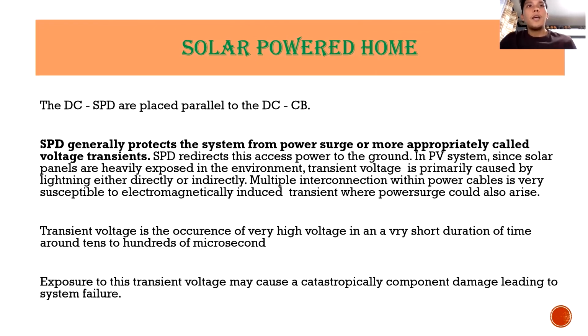Now for the DC side, SPDs are placed parallel to the DC CB. The SPD generally protects the system from power surge, or more appropriately called voltage transient. The SPD redirects this excess power to the ground. In PV systems, since solar panels are heavily exposed to the environment, transient voltage is primarily caused by lightning, either directly or indirectly. Multiple interconnections within power cables are very susceptible to electromagnetically induced transients, where a power surge could also arise. Transient voltage is the occurrence of high voltage in a very short duration of time, around 10 to hundreds of microseconds. Exposure to this transient voltage may cause catastrophic component damage leading to system failure.